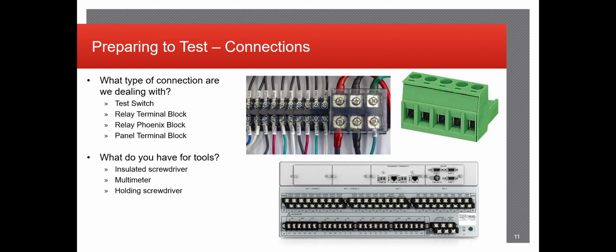Specific tools that you're definitely going to need if you're going to be relay testing are insulated screwdrivers, multimeters, and a holding screwdriver. The insulated screwdriver is always utilized by testing and commissioning engineers over just a standard metal screwdriver. This is because you understand that the relay, or any piece of equipment you may be using the screwdriver on, should have no power, no voltage or currents running through it, and no DC feeds. But sometimes you never know. You could test with your multimeter and then seconds later somehow it gets power, and if you don't have an insulated screwdriver, you could get shocked and possibly injured.